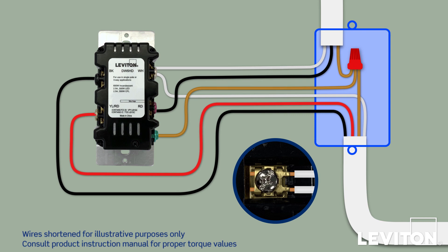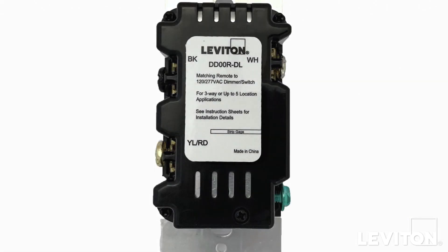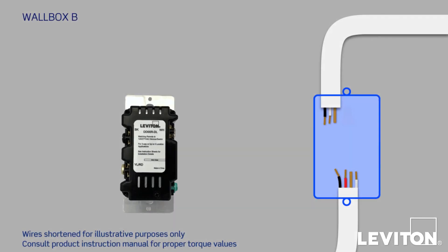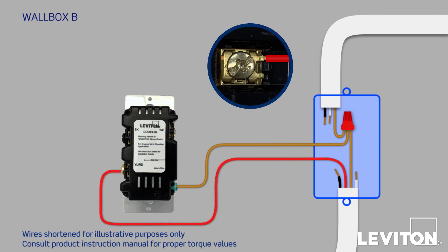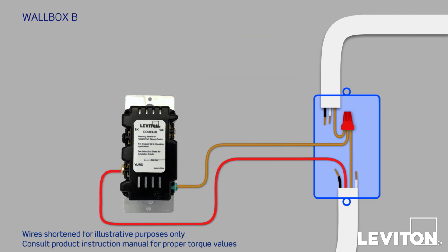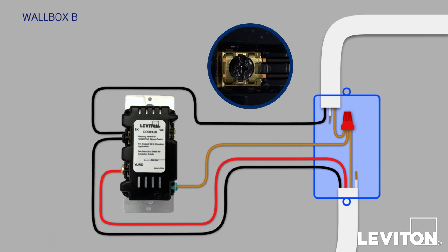Now let's install the remote device in Wallbox B — in this case, a Leviton DD00R-DL matching dimming remote. On the back, you'll see three screw terminals labeled BK, WH, and YL/RD, and a green ground screw. Start by pigtailing the two bare copper wires and firmly attaching the end of the pigtail to the green ground screw on the device. Now connect the red conductor from the Traveler to the YL/RD terminal. Next, take the two black conductors — one from the Traveler and one from the line wire — and connect them both to the BK terminal.